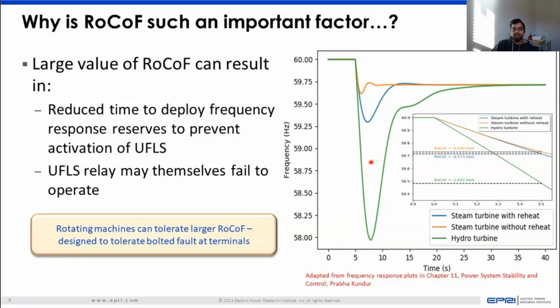So the main concern is that if we have inverter-based resources, then as long as we can do something with these resources to prevent operation of a UFLS relay, we should be good to go from a frequency response perspective. This doesn't imply that legacy protection thresholds or settings may not be impacted - that's something to tackle as we learn from operation of the power system. But the major concern is mitigating the rate of change of frequency from hitting the UFLS threshold with inverter-based resources.